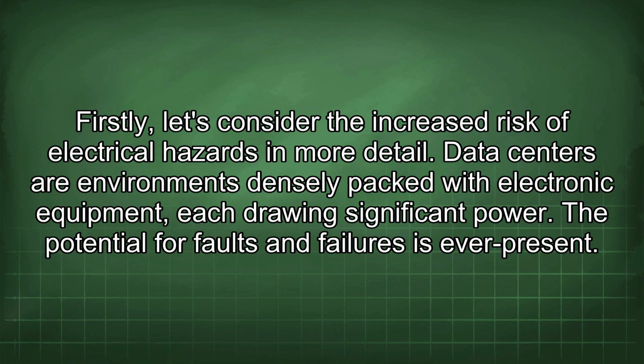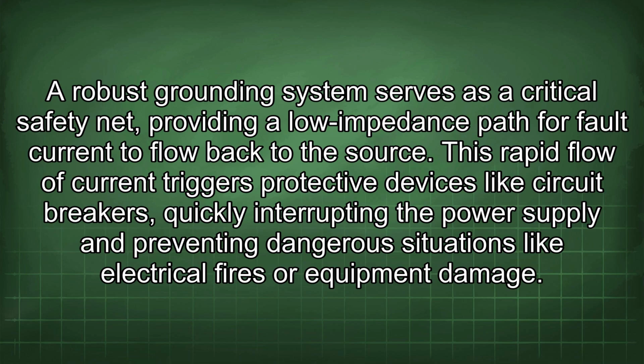Data centers are environments densely packed with electronic equipment, each drawing significant power. The potential for faults and failures is ever present. A robust grounding system serves as a critical safety net, providing a low impedance path for fault current to flow back to the source. This rapid flow of current triggers protective devices like circuit breakers, quickly interrupting the power supply and preventing dangerous situations like electrical fires or equipment damage.